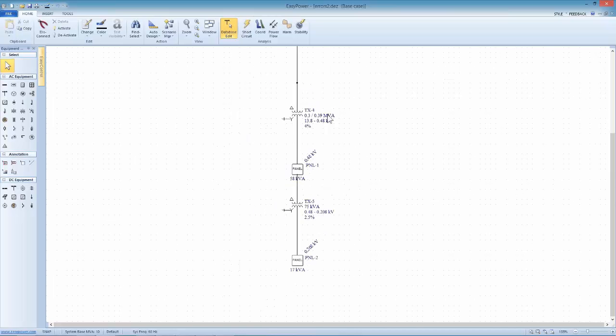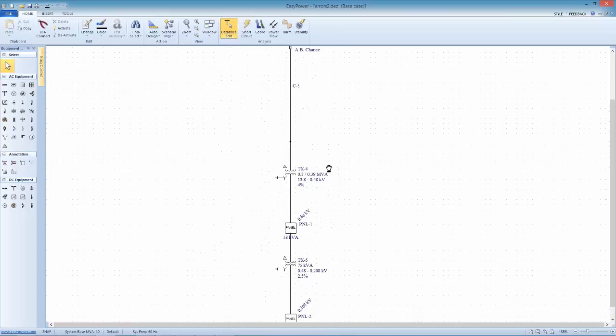Now, as I draw this, drawing the one-line is relatively straightforward. You'll notice I seem to have everything in line, and what most often happens on a first-time event, whether you have an extremely complex system or a modest one, so I endorse starting modest first so you don't spend a lot of time and then have to redo it later, is I changed focus from the database editor, which allowed me to draw the one-line diagram, to the short-circuit focus, and then I fault the buses.